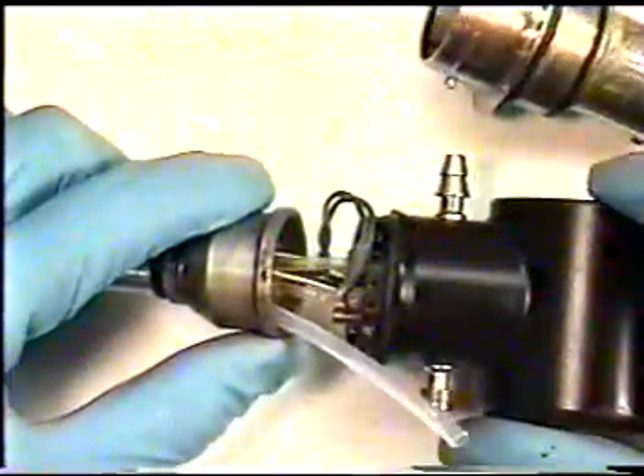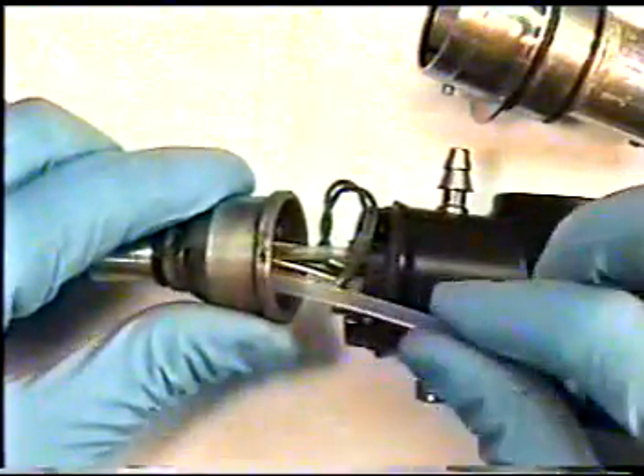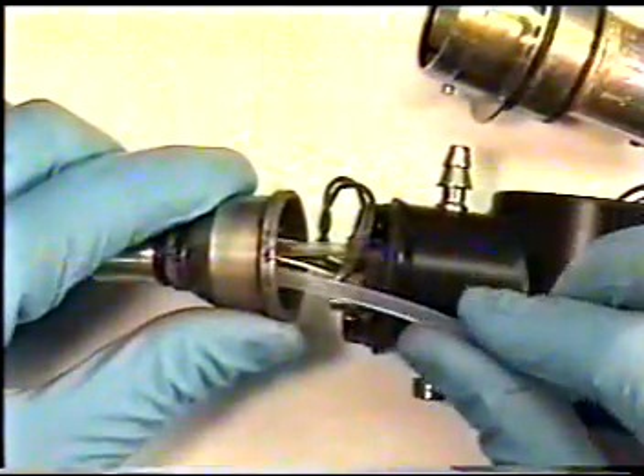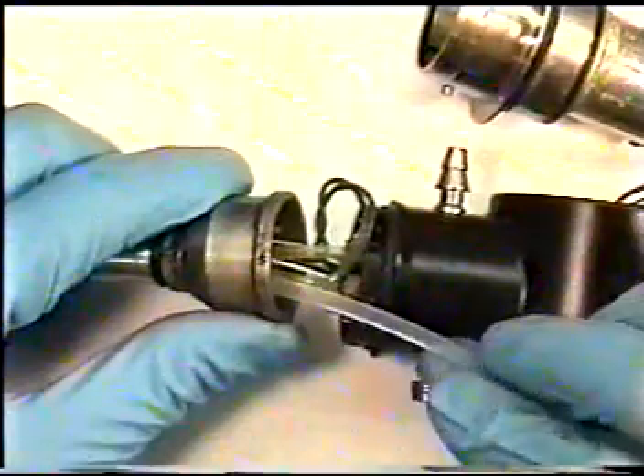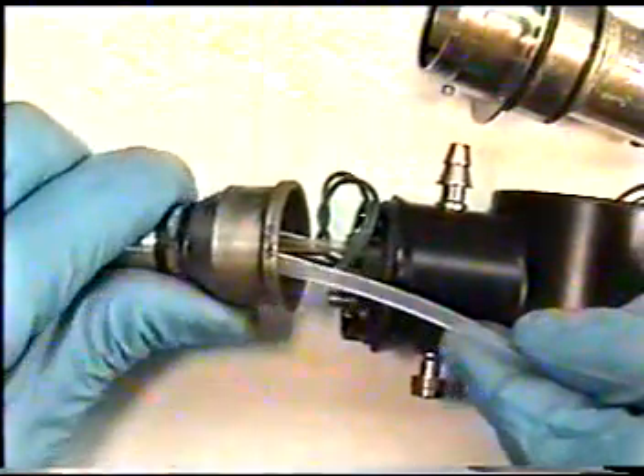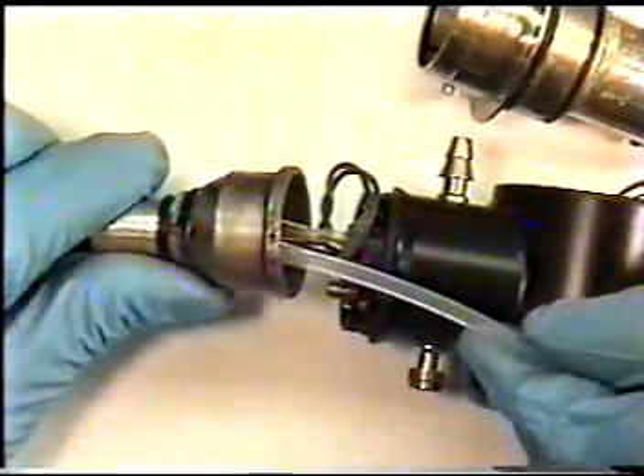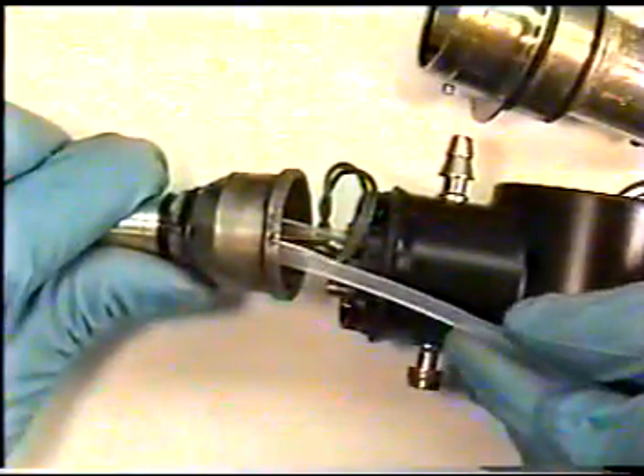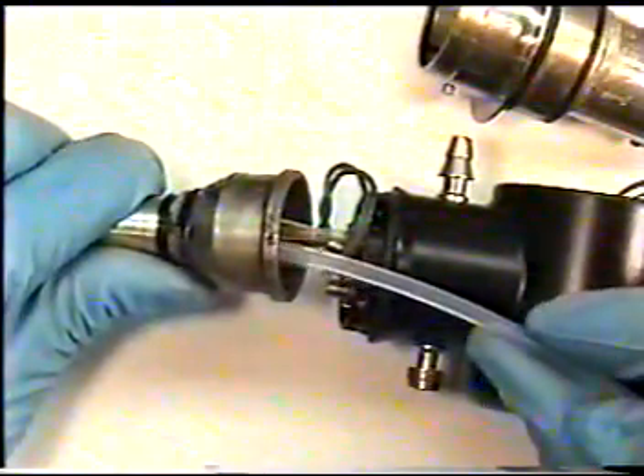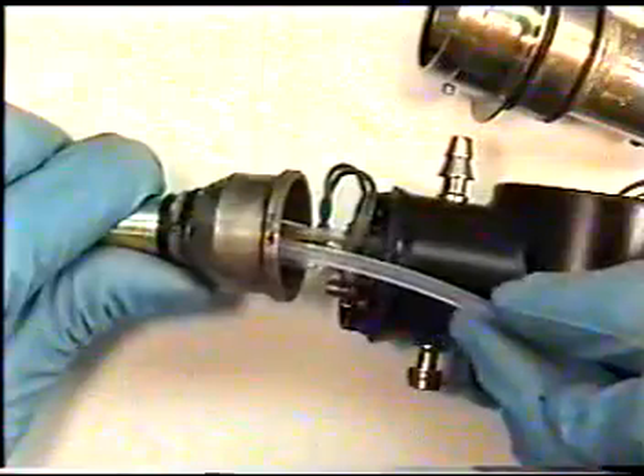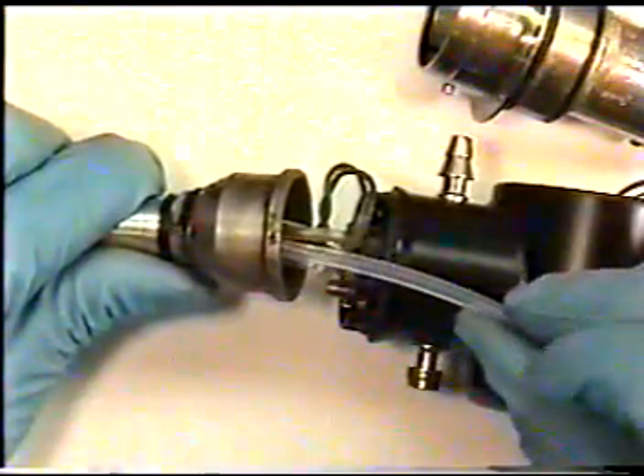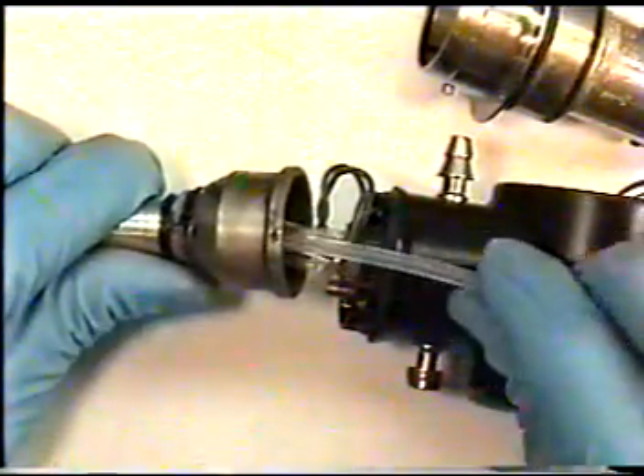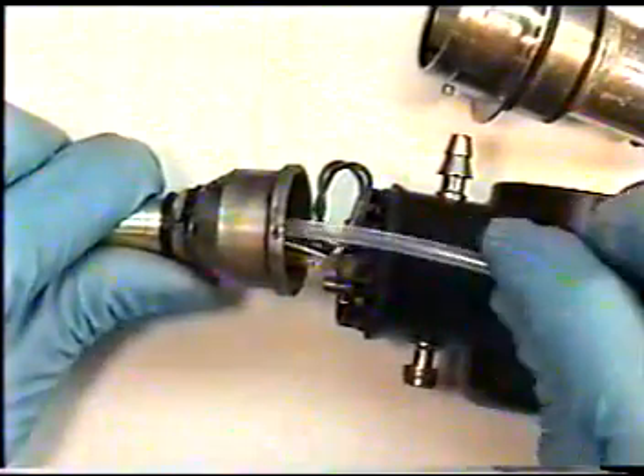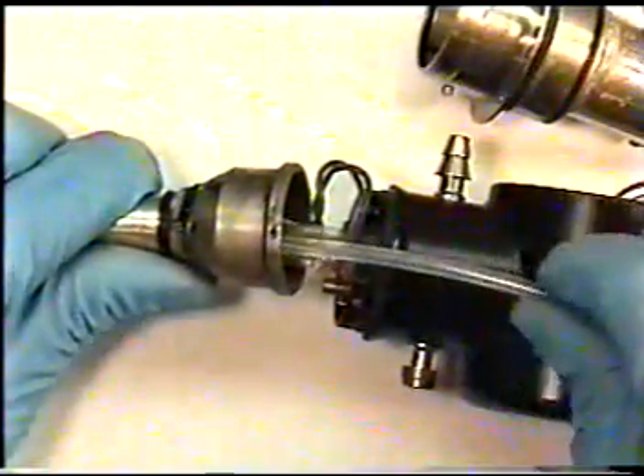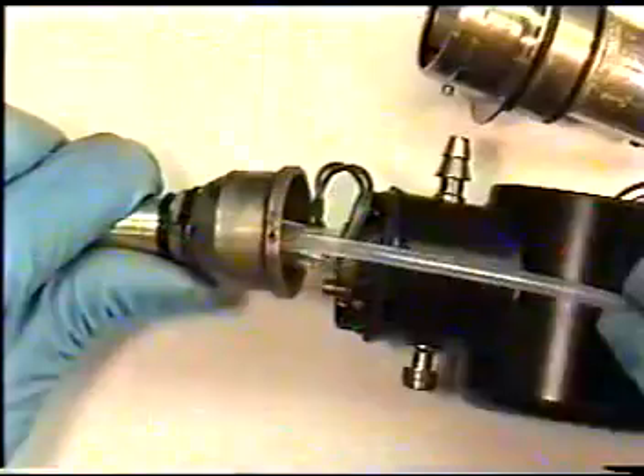Go back down to your connector section of the Olympus scope. We'll now pull through our brand new illumination light bundle. Be extremely cautious. This is a brand new illumination light bundle and you do not want to damage it. You can easily break the light guide fiber bundle by applying excess force against it. By pulling it too hard, you will cause damage to it, so be extremely careful while pulling through your new light guide bundle.